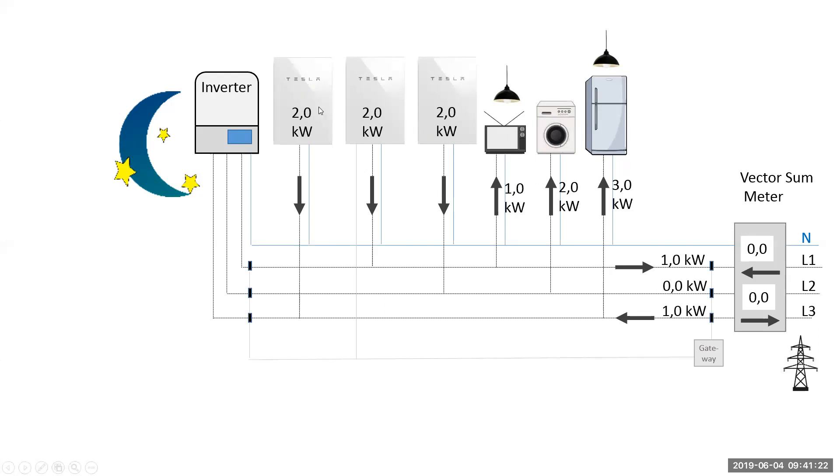Each of the batteries would be exporting two kilowatts to match the home load. In this case, it would mean one kilowatt is going out on L1 and one kilowatt is coming in on L3, but the vector sum meter will be zero.